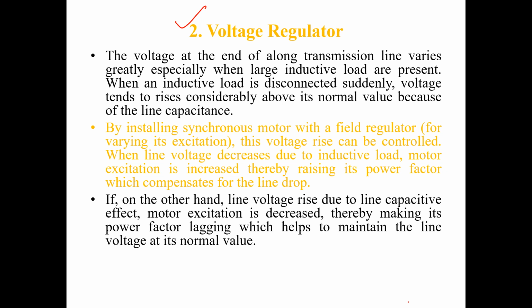compensate the line drop. That means the nature of the synchronous motor is that it can be operated at leading power factor and lagging power factor. If the voltage is rising and we want to reduce it, we use it at lagging power factor. If the voltage is falling and we want to increase it, we can operate at leading power factor. That means by changing excitation, by operating at different power factors, that motor can be used as a voltage regulator in a transmission line.